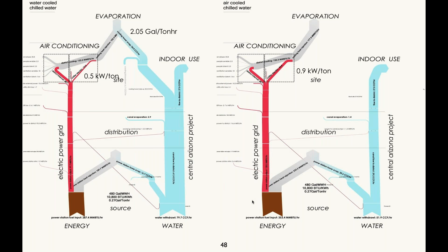But what you see here is if you had a 0.5 kW per ton on a water-cooled system and a 0.9 on an air-cooled system, yeah, we're using a lot more electricity on the air-cooled system, but the effect back at the power plant isn't as significant as you might think. So yeah, we're using more water in the case of an air-cooled chiller back at the plant, but it's not enough to compensate for the amount of extra water we're using in a water-cooled system.